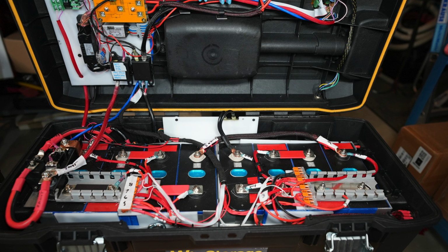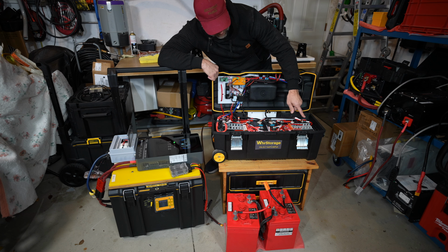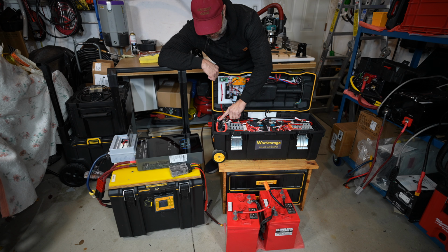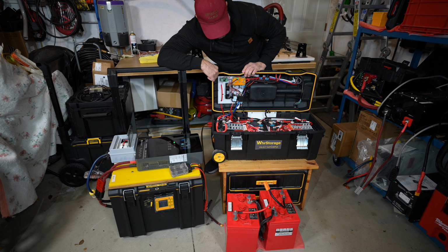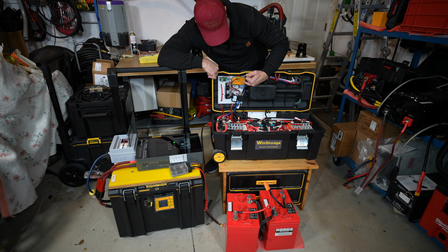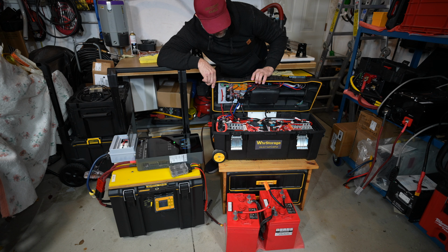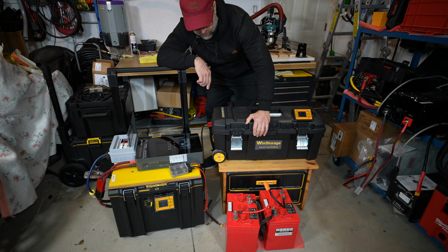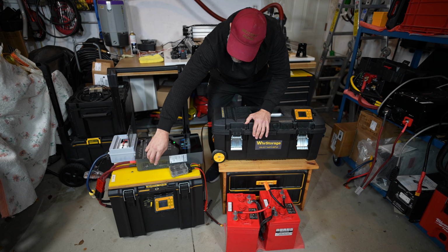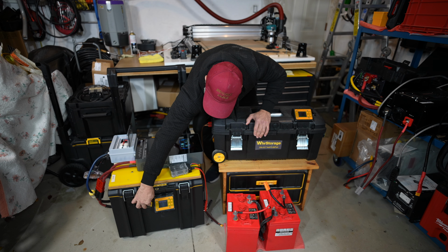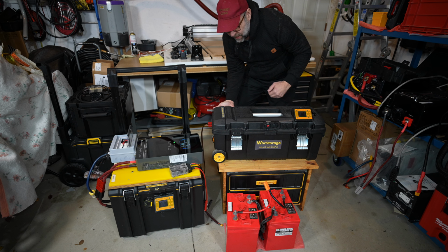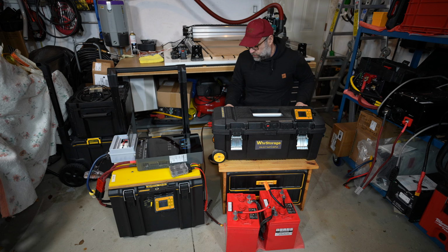Again, we've got two BMSs in here, one on the negative and one on the positive side, using a relay to disconnect the loads whenever the battery is fully charged. This here is the PV in, 50 amps per side, but I limited it down to 40 amps. Now this has a breaker here, and this one has two. Just have to trust me.